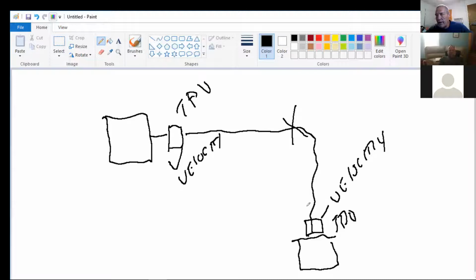When you're looking at transmission lines that span a large area, you can imagine trying to patrol all of that, whereas they can tell you—it takes about 15 minutes for them to calculate it out—they're able to say you need to go to structure 5, 6, 7, 8, 9, pull it up on a map, that's where the fault occurred, within 100 feet in either direction. It is pretty cool. I have to admit I was kind of skeptical about it, but I used it about a dozen times, and they were not wrong any of those times.